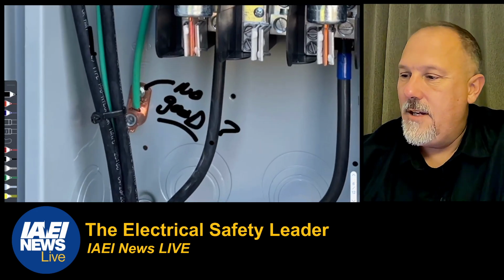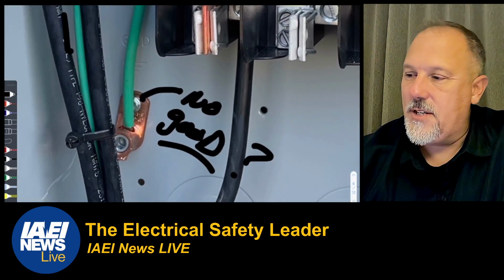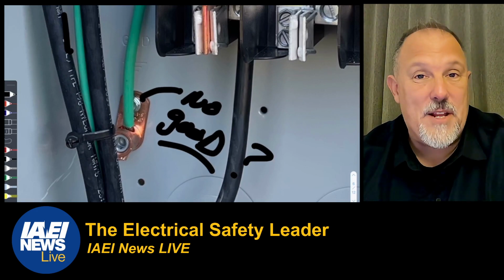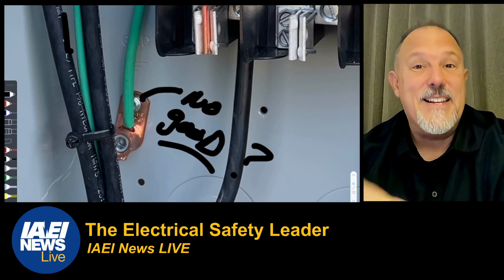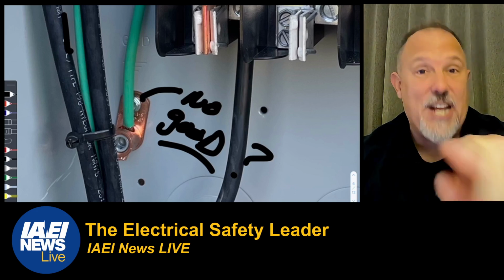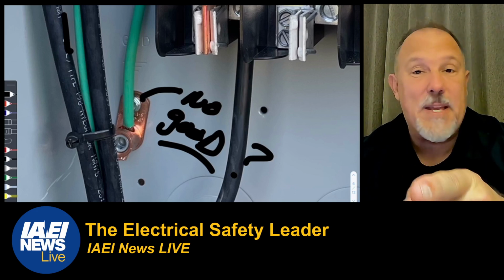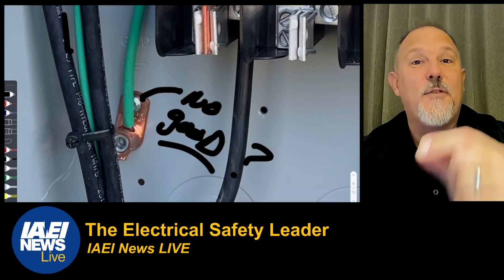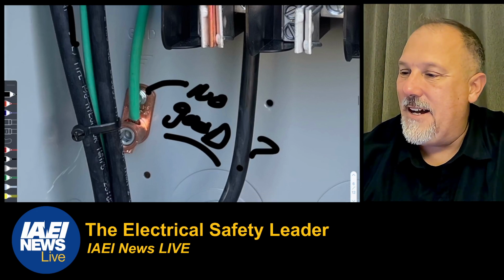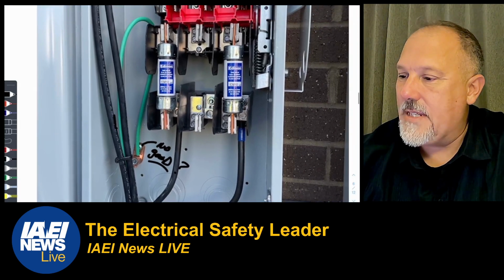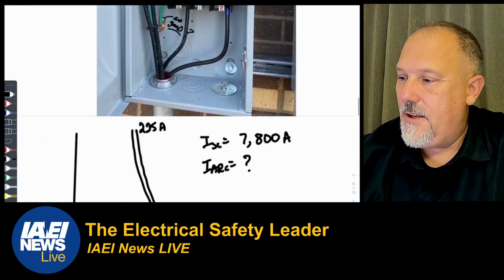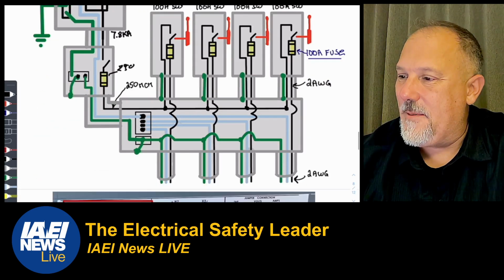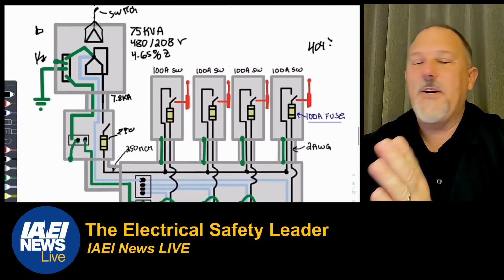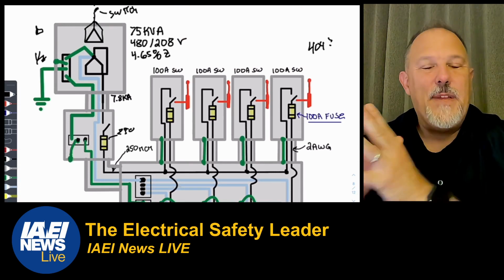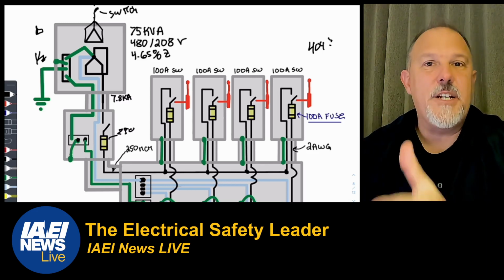How about this one? This is in those 100 amp switches. Is that a self-tapping screw? You're not allowed, right? We need to have so many threads, and there's an article and a section that tells us how many threads we're supposed to use. Put that in the chat. I'm counting on you. What section of the code tells me how many threads I need engaged for a bond for this grounding? What was the other one? So no ground on that one. What else? Anyway, I'm telling you, these types of examples are great teaching tools.